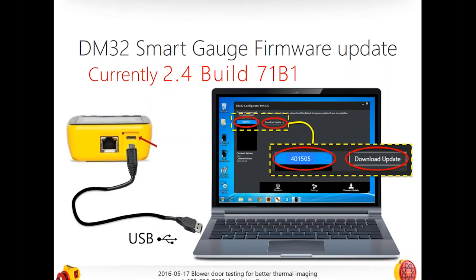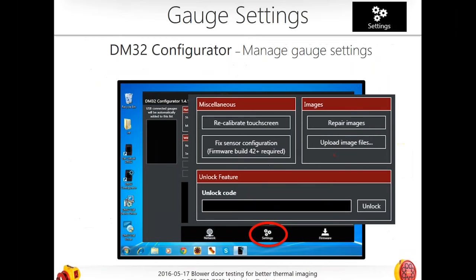Once you get the configurator open, you'll see three choices: networking, settings, and firmware. On the top left it will pop up and say which gauge it's connected to, and whether to download, update, or if it's up to date. If you have touchscreen calibration issues or the images seem off, go into settings, recalibrate, and update your firmware. If you have a non-Wi-Fi gauge and want to upgrade to Wi-Fi, this is where you'd enter your Wi-Fi code.